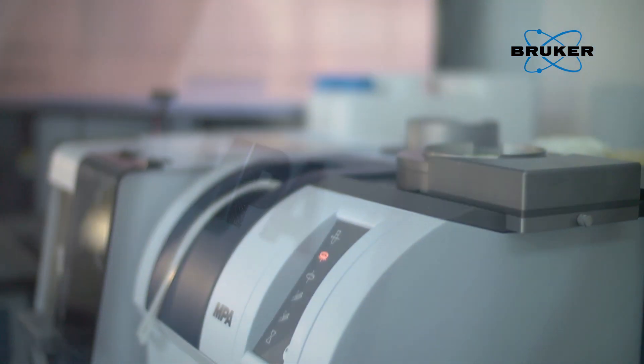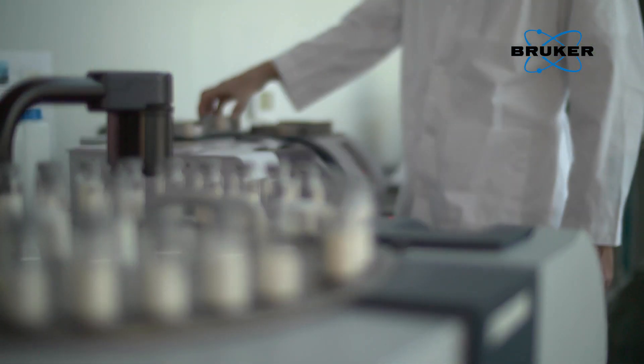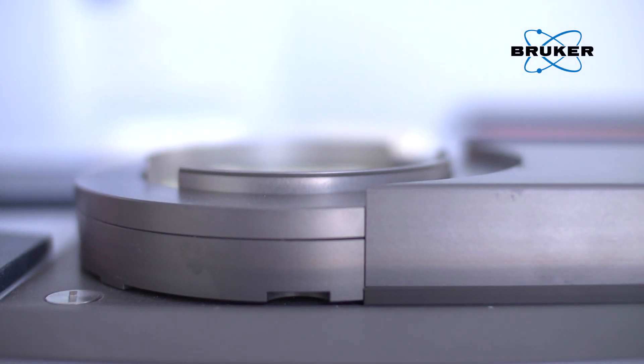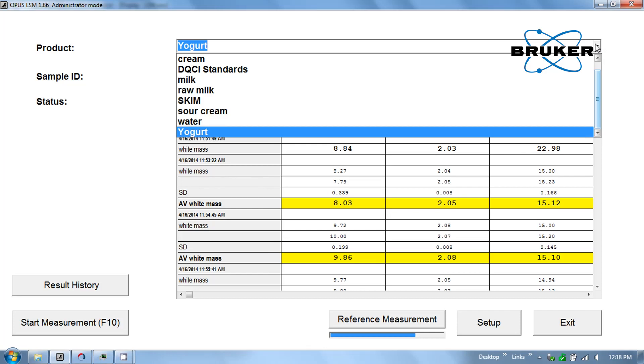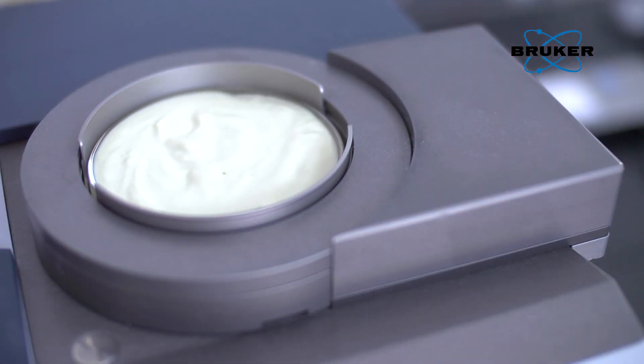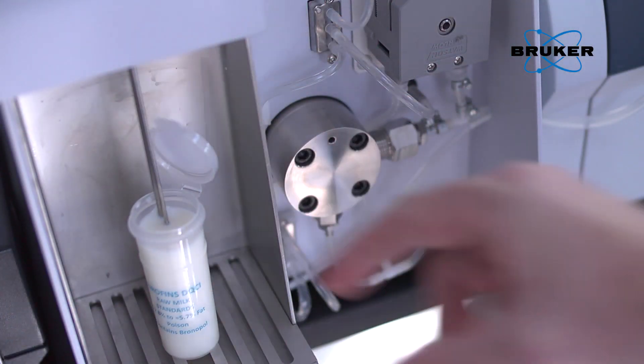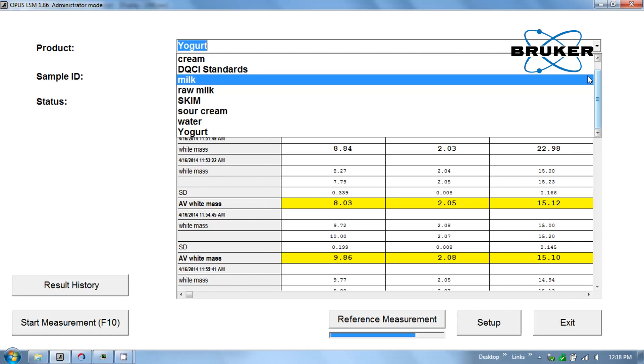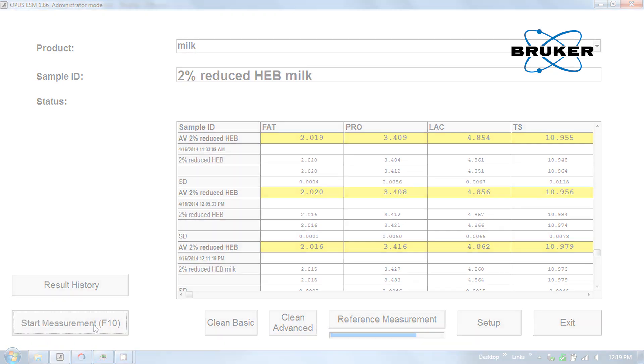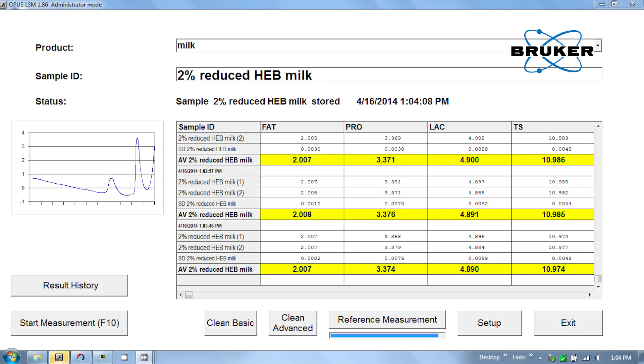The sample is measured internally along with the reference, and the shutter closes the mirror inside the machine. Without any operator influence, you can measure the sample by placing it on the loader. Using the pull-down menu, yogurt is selected and the measurement can begin. While the measurement is running, you can place a fluid milk, whey, or cream sample, select the product — in this case milk with 2% butter fat — from the drop-down menu, and start the measurement. The milk is pumped into the MPA through the homogenizer, and your results appear on screen.